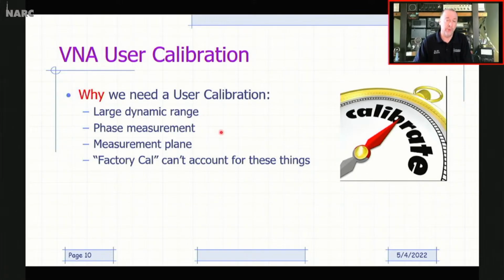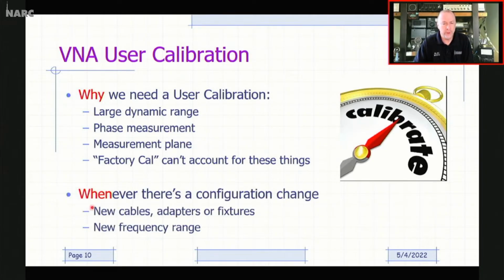That being said, can you get away without doing a calibration? Well, in some cases you certainly can, but in most cases you're going to get better results if you actually run the cal and use it. So when do we do a calibration? Whenever we have some kind of a configuration change. And usually that means one of two things. You're using a different set of cables or adapters or fixtures to get up to the device that you're measuring. And also anytime you change the frequency range that you're measuring over compared to the last time you ran the calibration. These are the two primary reasons why you'd want to rerun a user calibration.